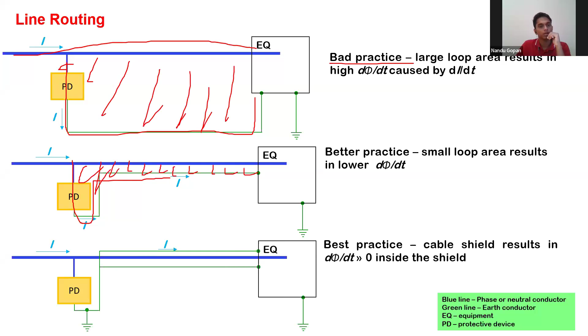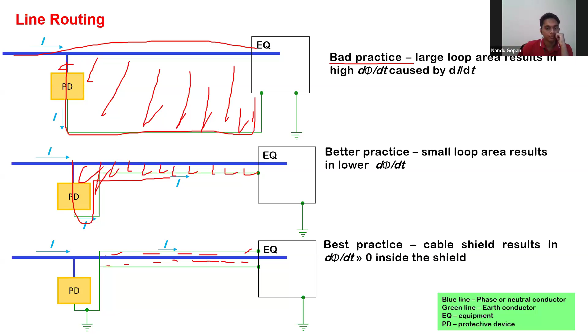So when doing line routing, take the P conductor - meaning the earth conductor - and the line conductor together. Don't bring them separate. That is very important. You are not supposed to have the line conductor here and the P conductor two to three meters away. Keep them together. If you're running a strip, run it along with the conductor - don't run it separate, don't run it five to six meters apart. It is not good practice.